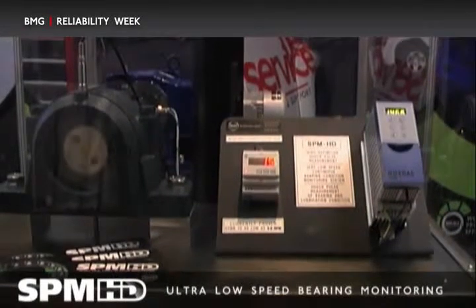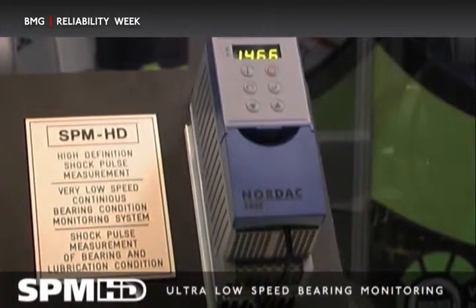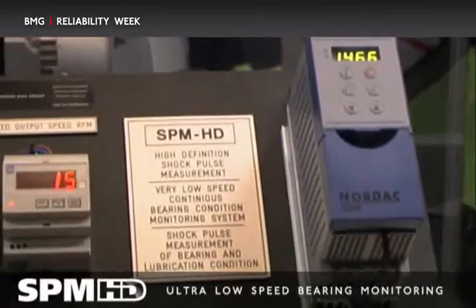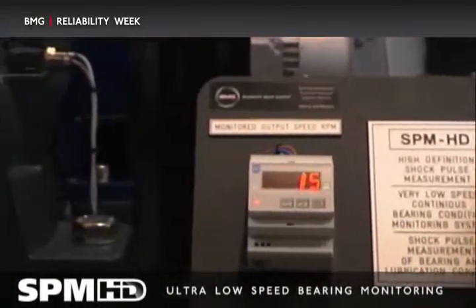As Dave mentioned, SPM HD has specifically been designed for slow rotational speed applications. Today on display here we have induced a bearing defect, and currently we are rotating at 15 RPM. By making use of the shock pulse transducer, which is permanently installed on the housing, we are able to continuously monitor this bearing defect with the application rotating at 15 revolutions per minute.